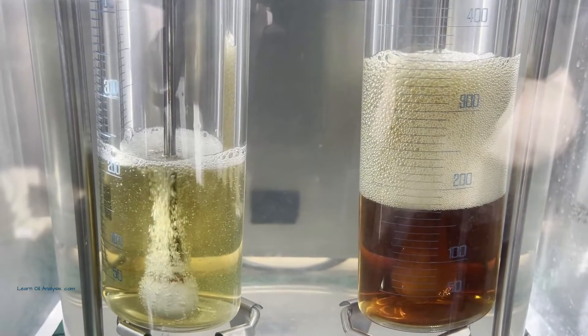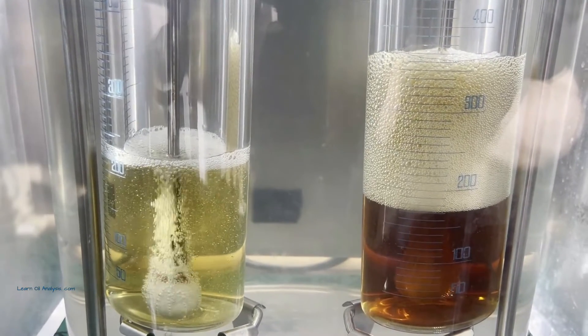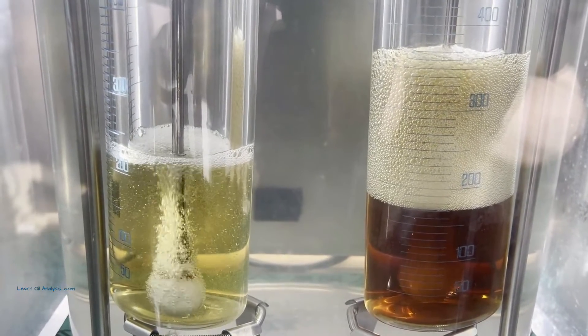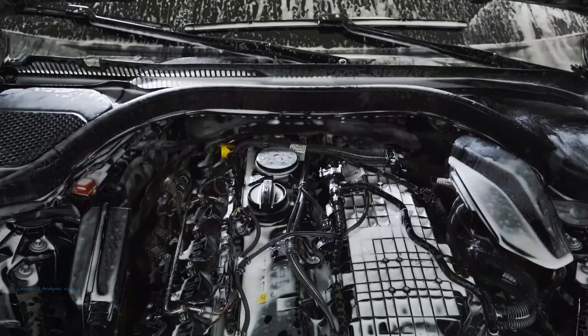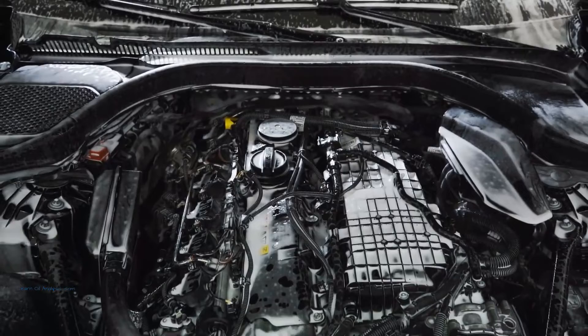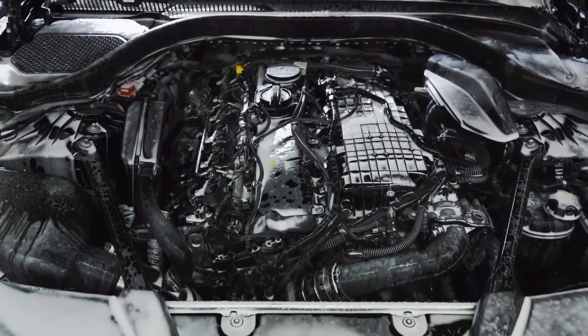Sequence 3 is a combination of Sequence 2 followed by Sequence 1 on the same sample, essentially a stress test for your oil first hot then cold. And then there's Sequence 4. This is the ultimate challenge, designed for engine oils and transmission fluids and not really used on turbines and hydraulics.